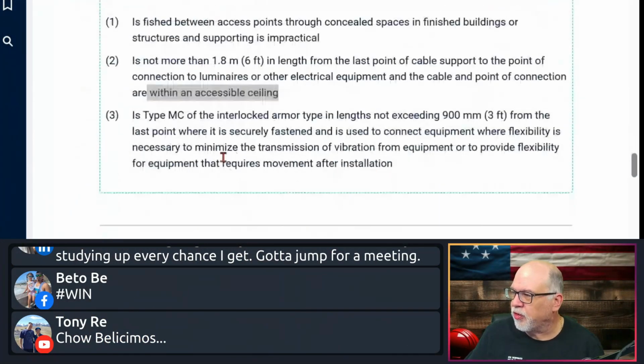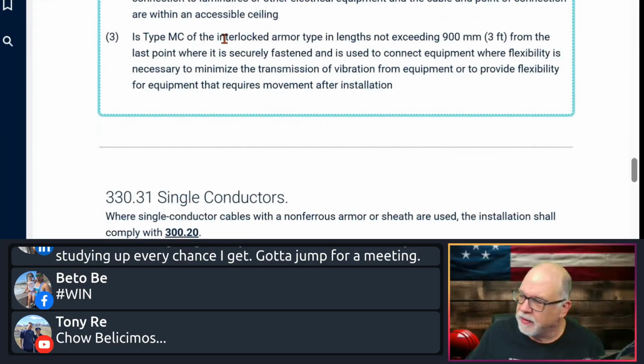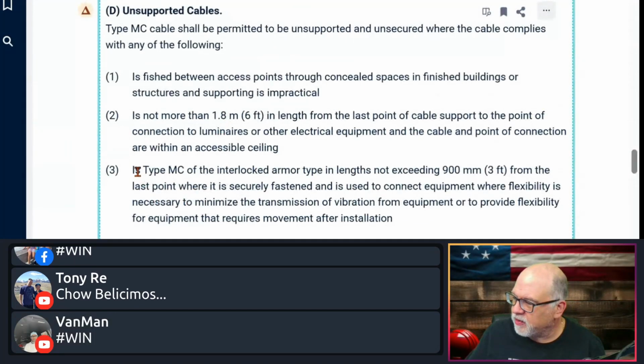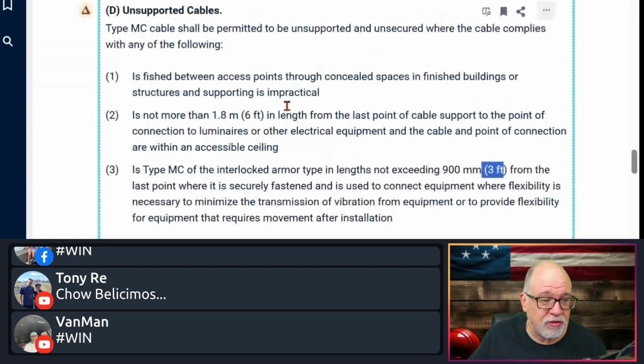Okay, so then the third one is type MC of the interlocked armor type, in lengths not exceeding 3 feet from the last point where it's securely fastened, and is used to connect equipment where flexibility is necessary to minimize the transmission of vibration from equipment, or to provide flexibility for equipment that requires movement after installation. Okay. So you have an allowance, by the way.